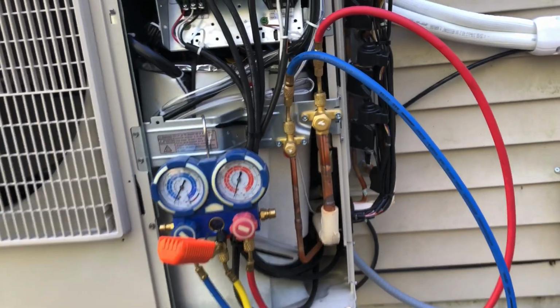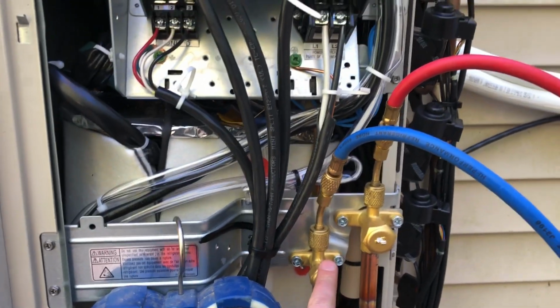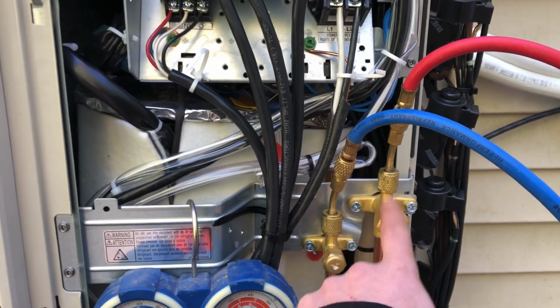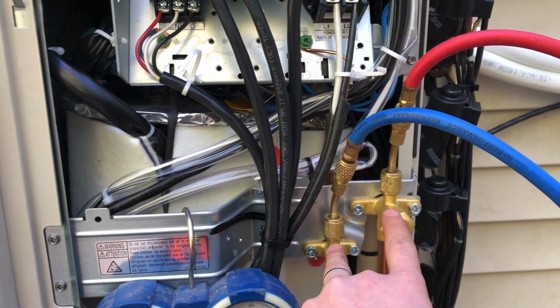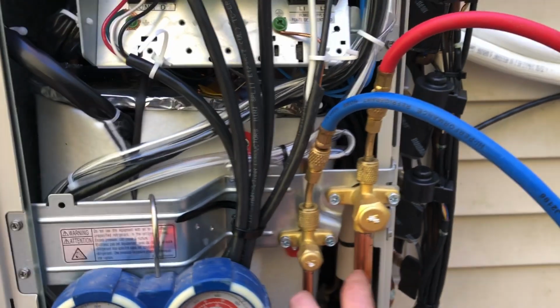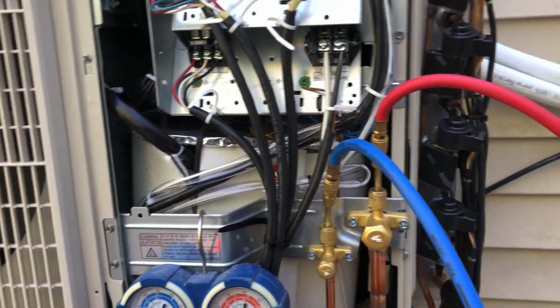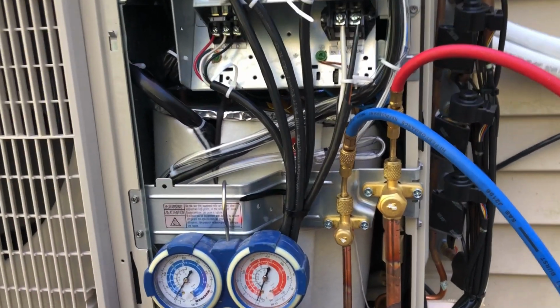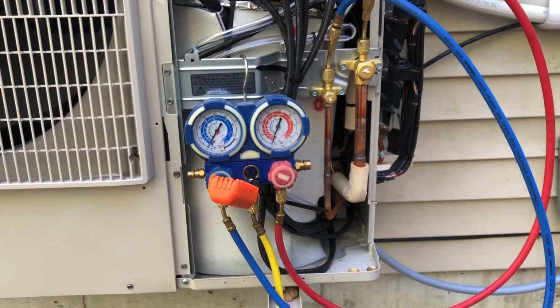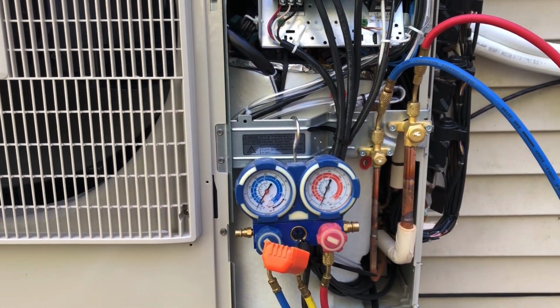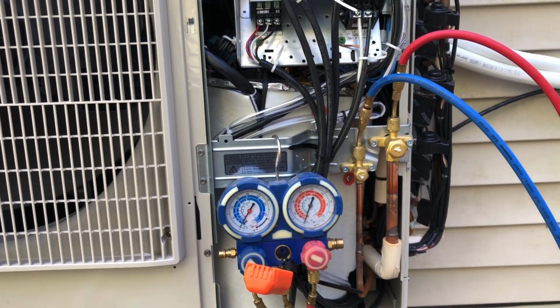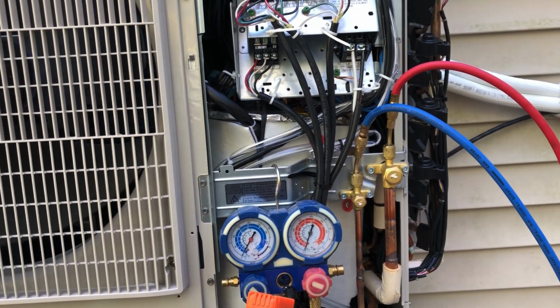So what you see here is I've opened up the panel. This is where you've got your liquid side and gas side refrigerant lines, and this is how you hook up. Right now I've done nothing to the unit other than open it up, and I've hooked my hoses up to the high and low pressure side, the liquid and gas side.